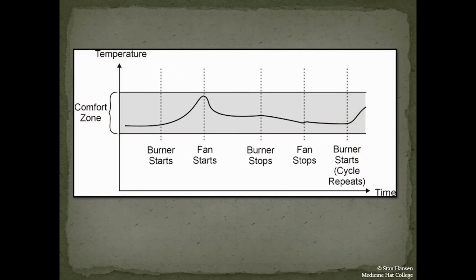We also need to consider how closely our two set points are to each other. If they're set too closely, it will create what's called unwanted cycling. As soon as my fan starts, we notice that there's a significant drop in temperature inside the plenum, since it is mixing cooler air with the heated air. If that temperature drops below the off point, it will turn the fan off, which will allow the duct to heat up again to the point of the fan on, which will drop below the fan off point. This cycling can cause premature wearing of the motor as well as multiple other problems within your furnace.